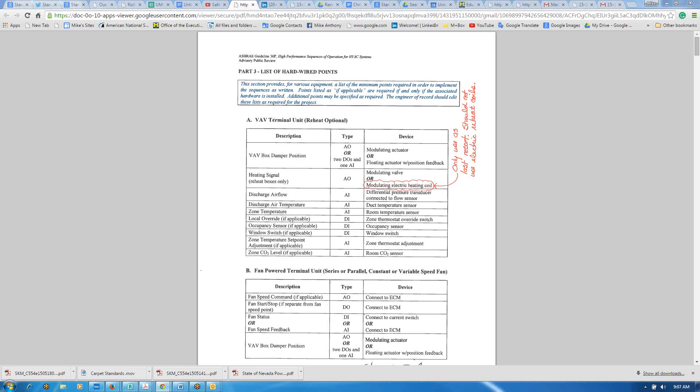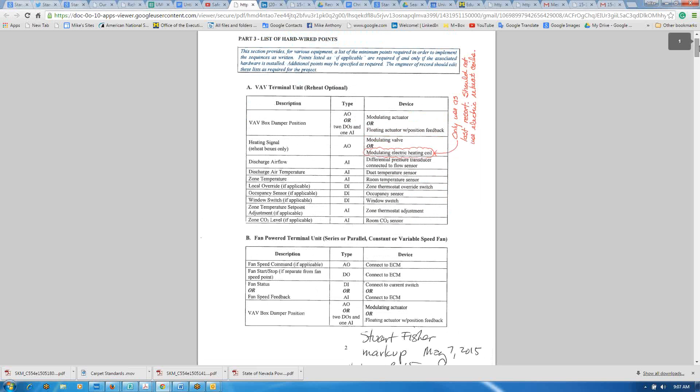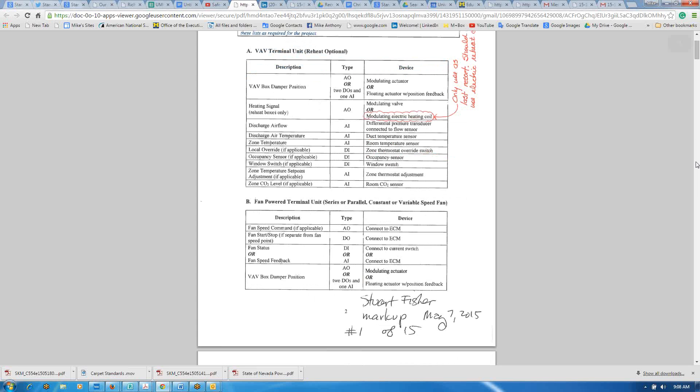I'd like to thank everybody for giving me the opportunity to review the guidelines. Starting on page 2 under paragraph A on heating signal, it has modulating valve or modulating electric heating coil. I have a concern with that. I put a comment that the electric heating coil should only be used as a last resort. I've had bad experience with using heating coils for tempering. They're great for less expensive first cost, but I've run into experience where they're a nightmare when it comes to operating costs and maintenance costs.